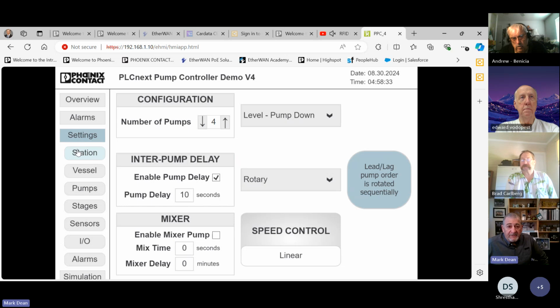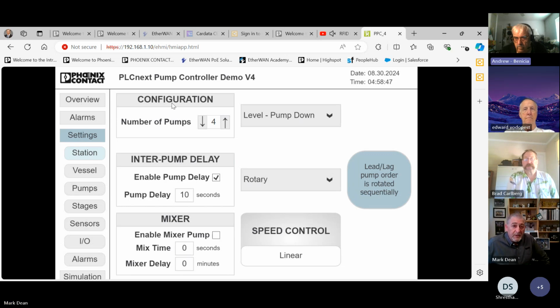Now we're looking at the station tab. Here you can configure this pump controller application to have 1 to 4 pumps. Ours had 4 pumps -- remember though, there's only 1 vessel, so if we're using 4 pumps, it's probably a very large vessel. Now, between pumps turning on, there's a big inrush of power when a pump turns on, so we might want to add some delay there. Here I've got a 10-second delay between pumps starting.